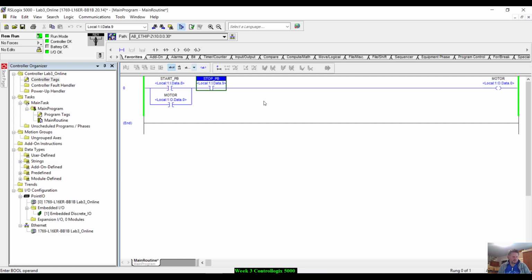So now at this very moment, I can do some testing here. So I've got stop push button. It's actually a toggle, so I'm going to go ahead and toggle him on. So now my stop is on. And if I hit my start button, just as a brief bump, that guy comes and seals this guy in. What happens is it closes that contact. As you can see, this is still on. This is on now, and this is transferring power to this guy to keep him on. The only way to turn him off is by hitting that stop button. And that drops him out.